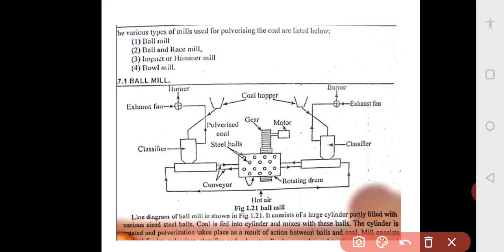Feeders supply the coal to the classifier and it is passed to the pulverizer with the screw conveyor. A mixture of tempering air and hot air from the air preheater is introduced in the pulverizer. These streams of air pick up the pulverized coal and pass through the classifier.